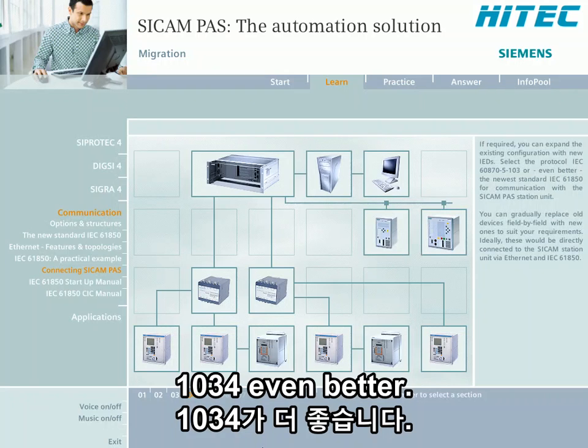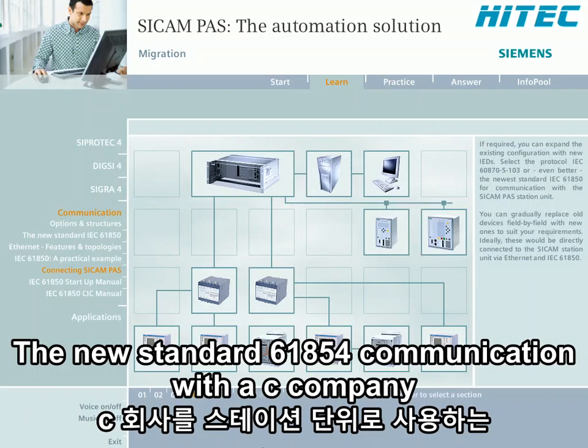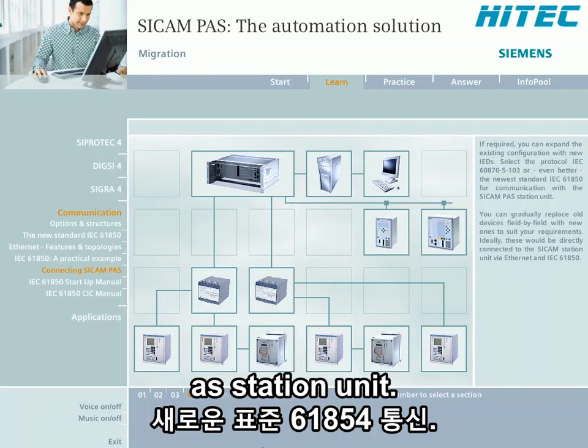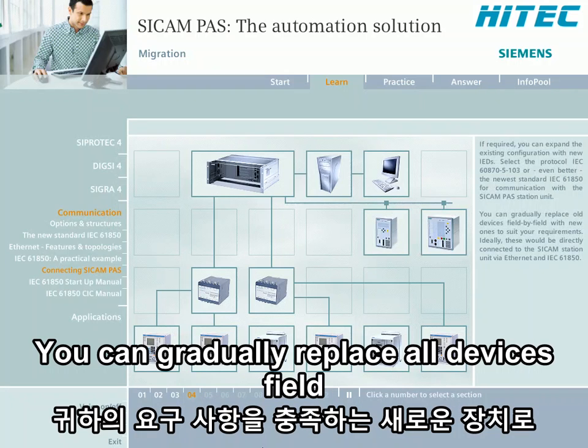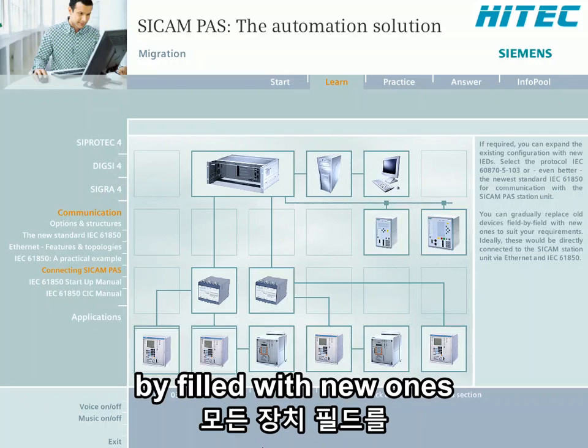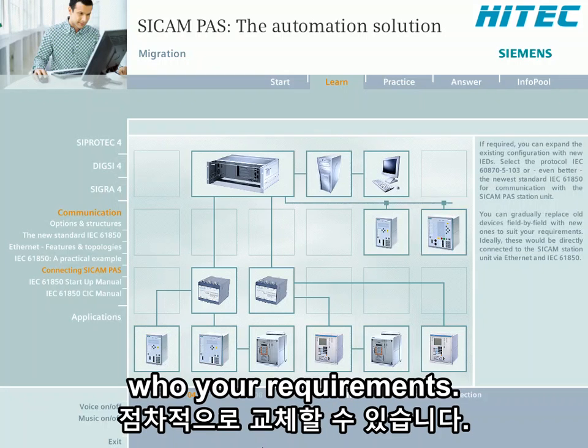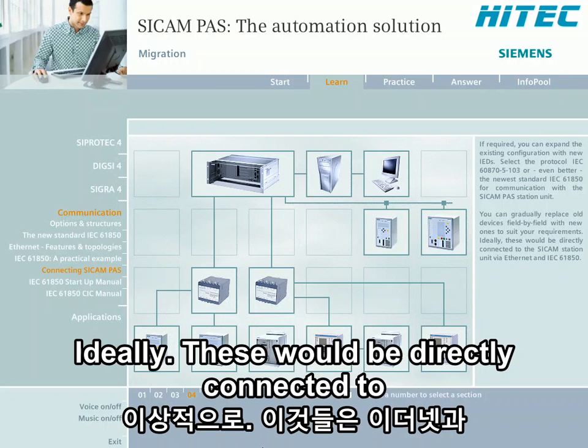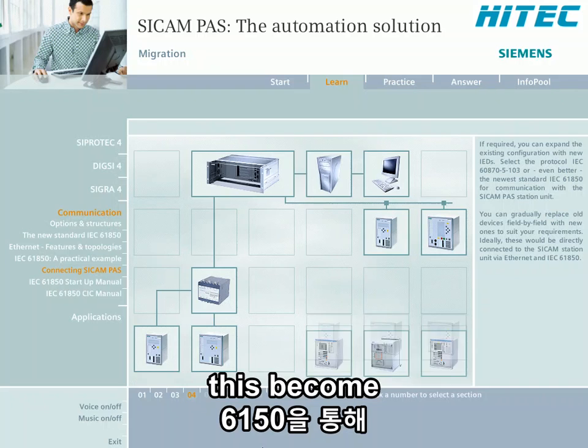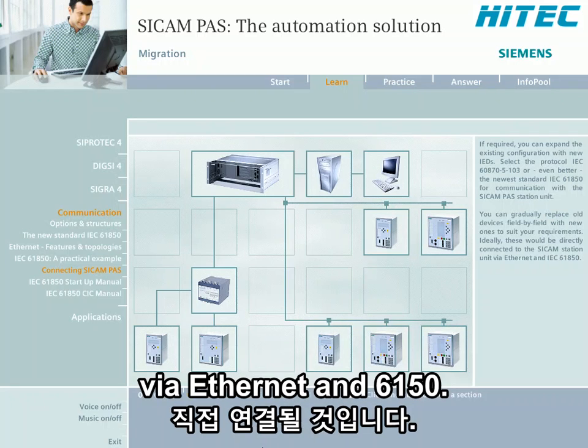Select the protocol IEC 60870-5-103, or even better, the newest standard IEC 61850 for communication with the SICAM PAS station unit. You can gradually replace old devices field by field with new ones to suit your requirements. Ideally, these would be directly connected to the SICAM station unit via Ethernet and IEC 61850.